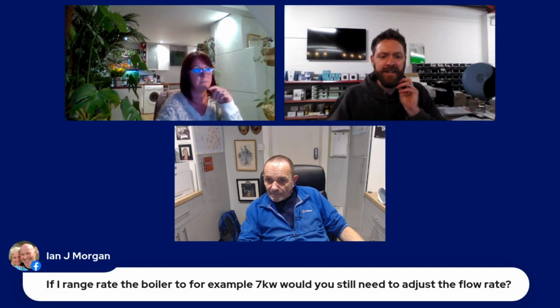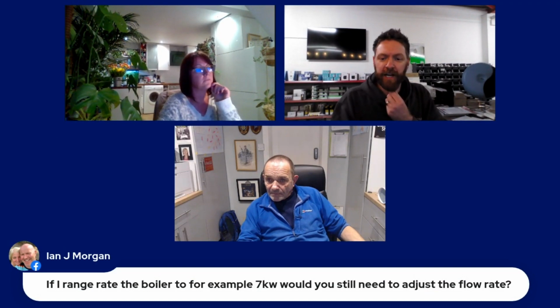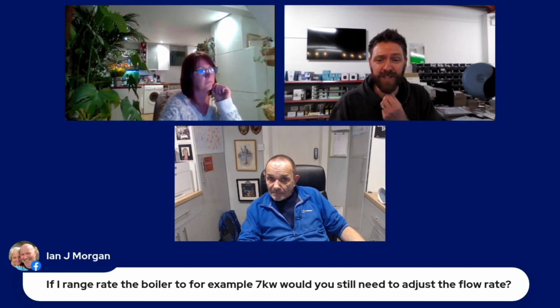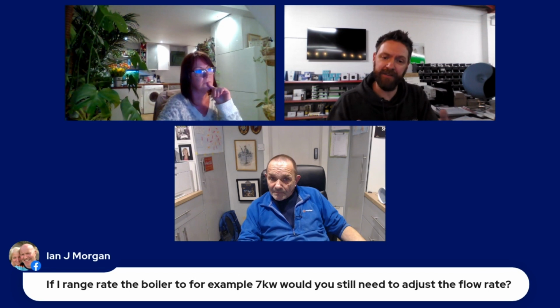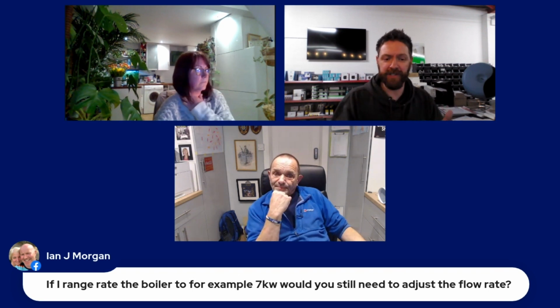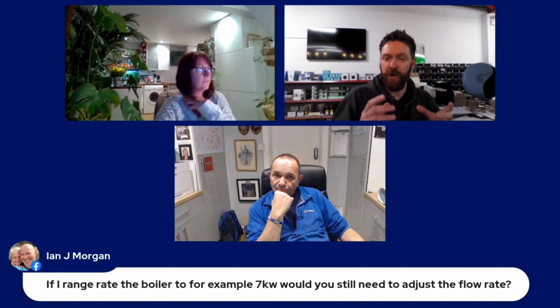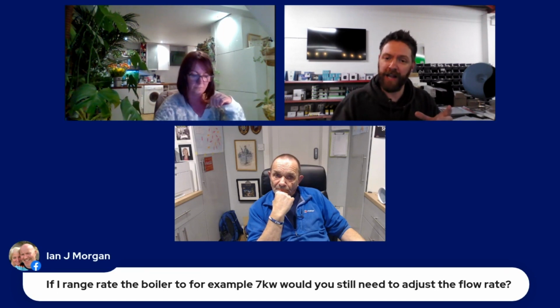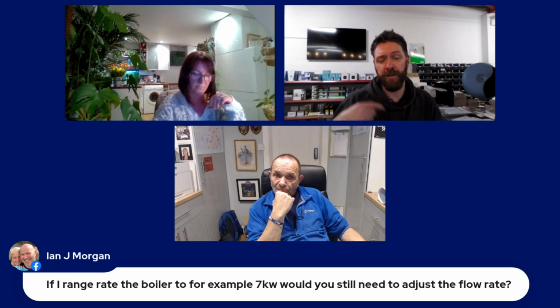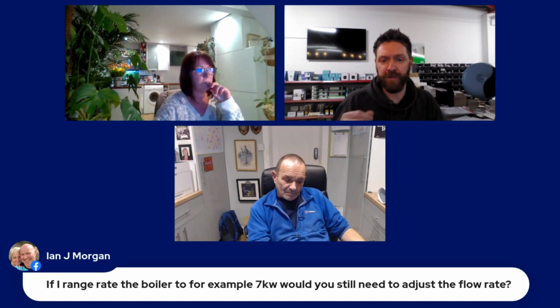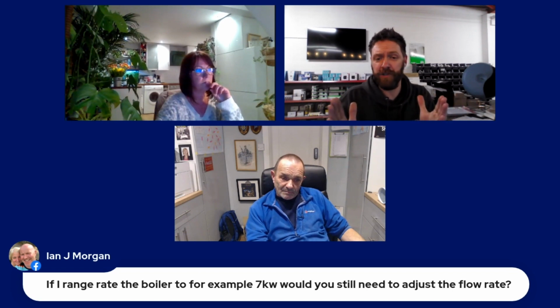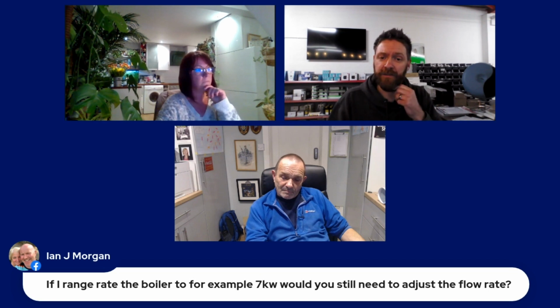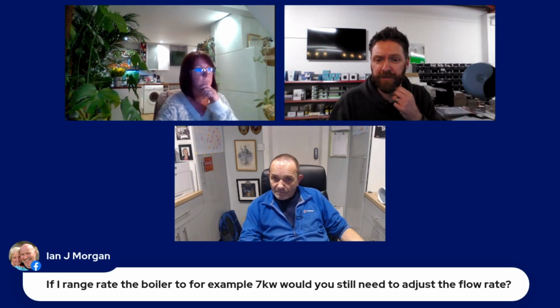There's a question up there, I think it was from Ian. He said, if I range rate the boiler, for example, to 7 kilowatts, do you still need to adjust the flow rate? Well, the answer is yes, because why would you want more flow rate than the actual output of the appliance? If your output is 7 kilowatts, you only need a given flow rate for that amount of output going into that space heating circuit. If you've got too much flow, you're still going to have your 7 kilowatts going into that circuit, but you've got a very good chance of narrowing the DTs of that heating circuit, or it's going to be much more difficult to balance.